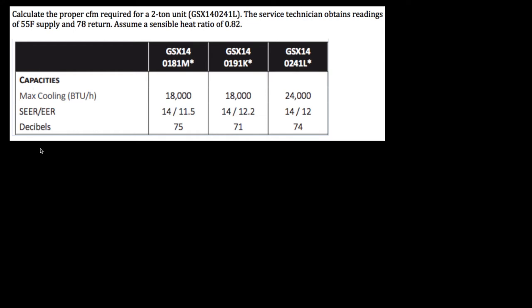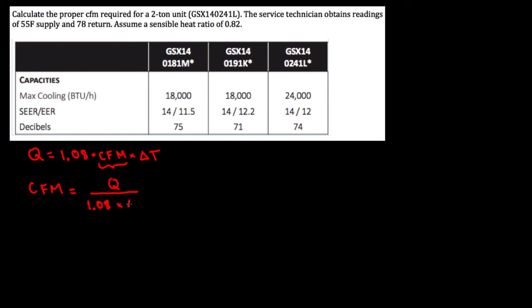The sensible heat equation indicates that Q equals 1.08 times CFM times delta T. So if we want to obtain the CFM, we're going to solve for CFM. CFM equals Q divided by 1.08 times delta T.